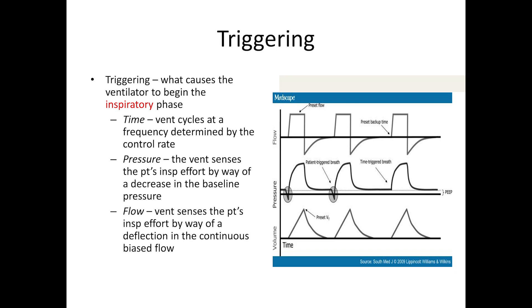For some patients, the trigger is time. We can set the mechanical ventilator to a certain rate, and if we set a number of breaths per minute at 10, then every six seconds the ventilator will look to deliver a breath.